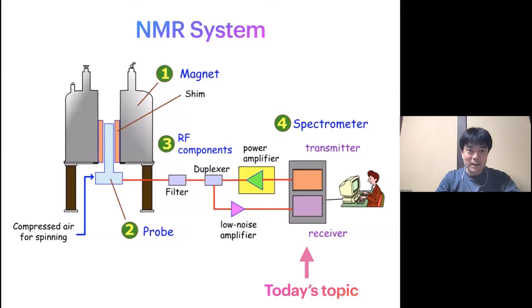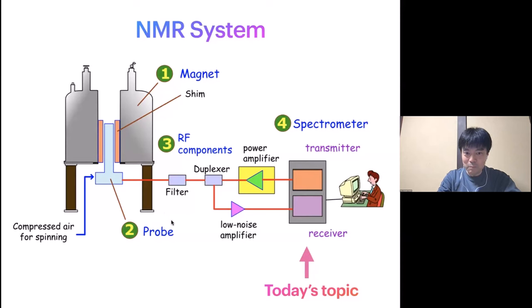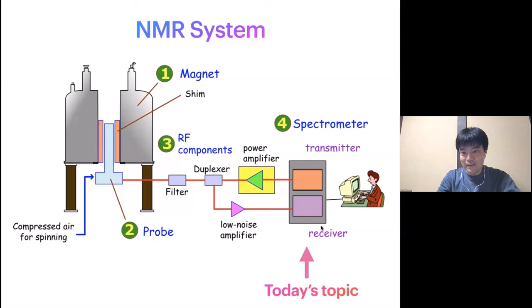Very roughly speaking, an NMR system is composed of: firstly a magnet, then a probe, RF components, and the spectrometer. There are already very nice lectures about probes in this global NMR series, so I would like to focus on something else — namely the spectrometer. And again, very roughly speaking, the spectrometer is composed of a transmitter and a receiver. Those are what I'm going to focus on today.